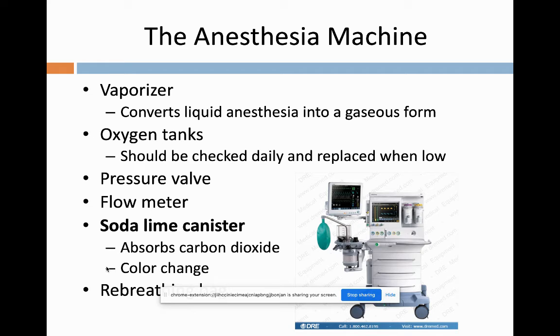Its job is to convert liquid anesthesia, the medication, into a gaseous form. It vaporizes that and applies it to the patient. Oxygen is also applied to the patient as well, with oxygen flow monitored. There's a pressure valve, flow meter, and a rebreathing machine.